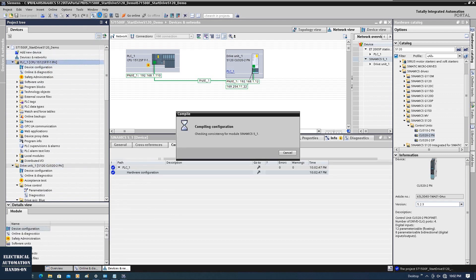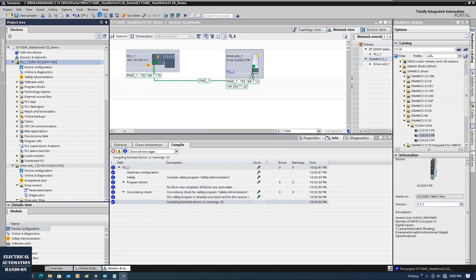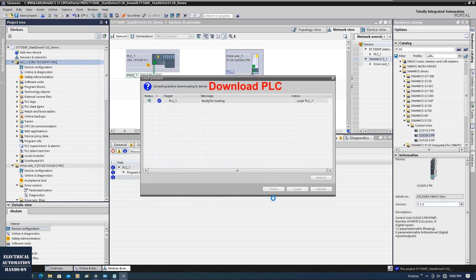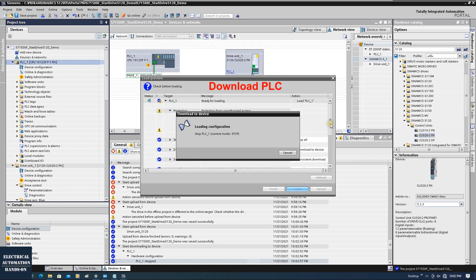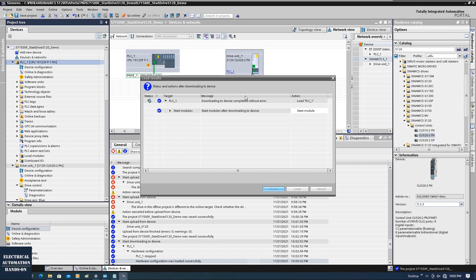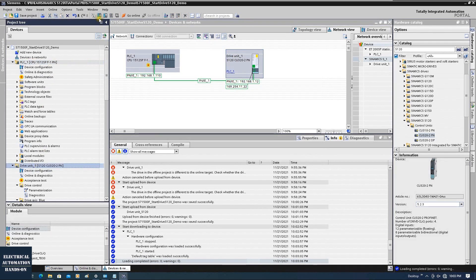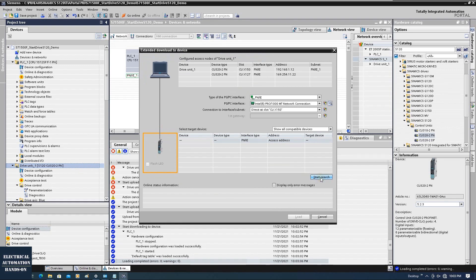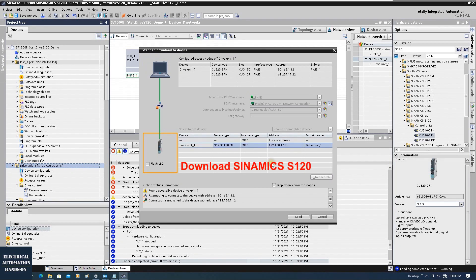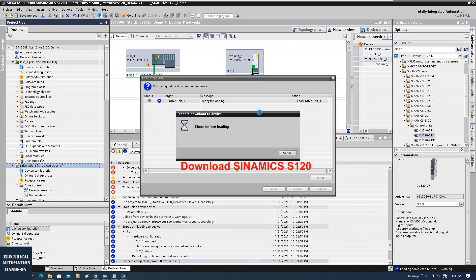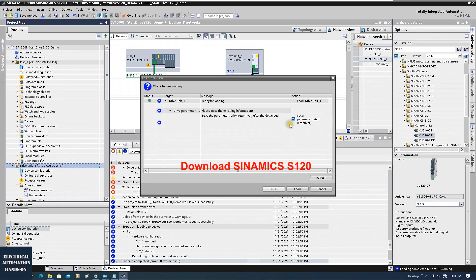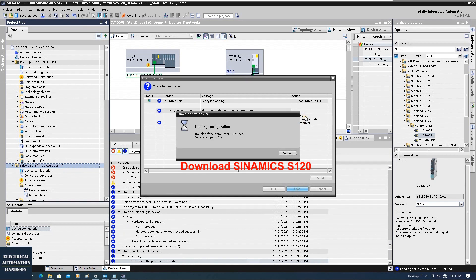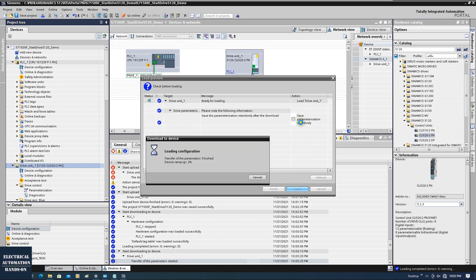Now let's compile and download the PLC hardware configuration — download this 1512 SP. The CPU will stop. This lets the PLC know it has one device — the S120 servo drive — as its slave. Then let's download this drive station. We can see the device name temporarily named 'drive_unit_1'. I will temporarily uncheck 'Copy RAM to ROM' to make this configuration download faster. Eventually, after everything is reconfigured, we can enable that selection.